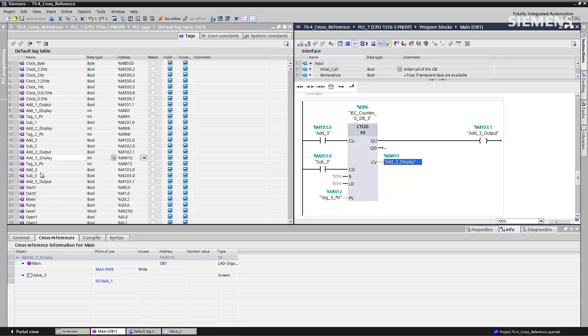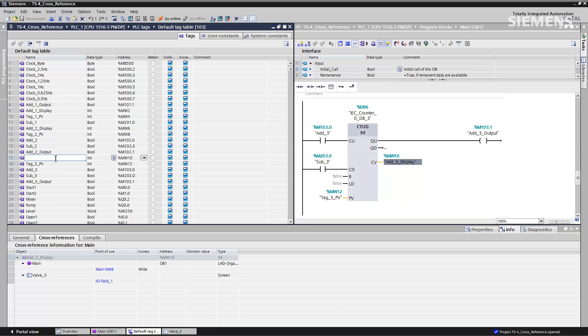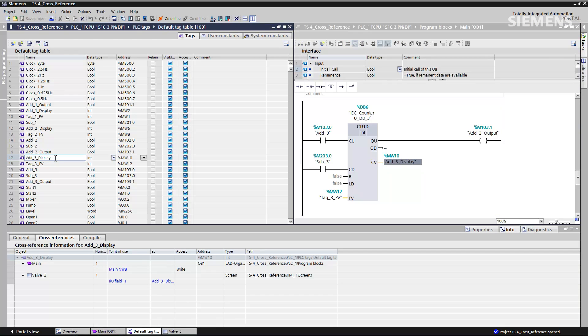If I want to change this, if I want to do a universal change, all I need to do is come back to the tag in the tag database, give focus to it, and change the name, let's say, underscore 2. Click on enter, and you'll see it automatically changes it even in the code. It'll do this for an entire automation architecture, and all I had to do was change it in one spot.